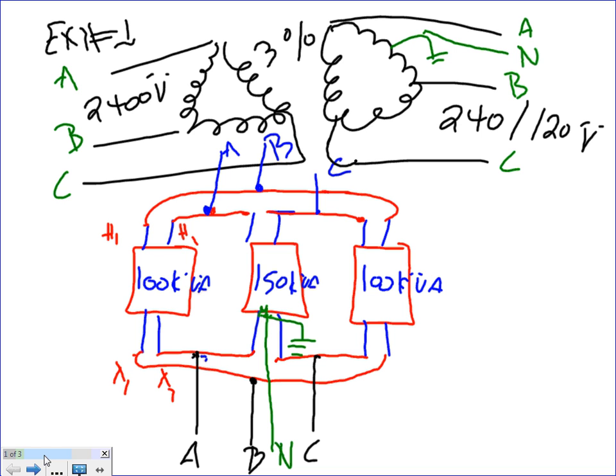And always the B will be here, because remember that wild leg, the orange leg, that's the B. Phase to neutral is going to be 208 - that's where the phase to neutral. See how in my case here I had it wrong - thank you for bringing this to my attention. This should be C here, and this one should be B. Anybody know why? Because the B is always the wild leg. The wild leg, from here to here, the voltage is always 208. That's the one you're not supposed to use. So A and C are always across this one here - A and C.